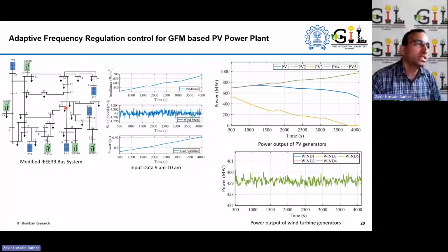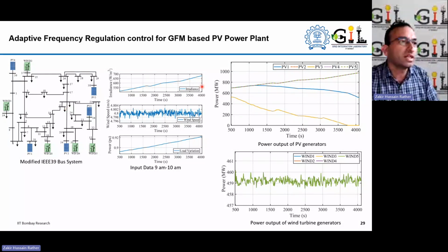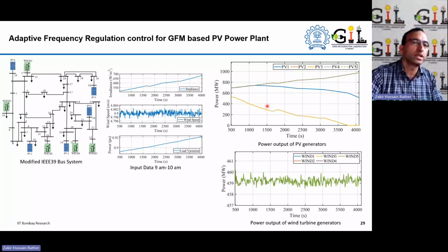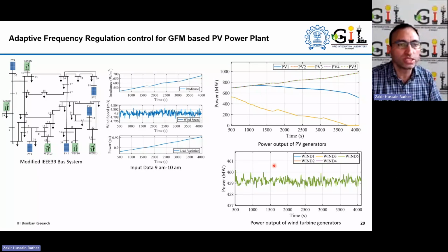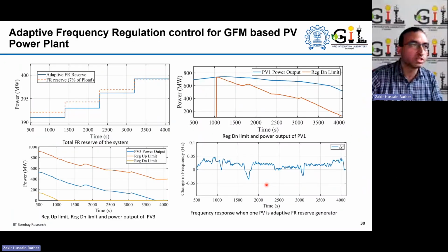So what the aim was here is the entire reserves. Of course, here there are no conventional generators, so the entire frequency reserves are provided by the solar power plants of the system, which are of the grid forming technology. So this is the irradiance variation that is considered for this window, and this is the wind speed variation, which is again considered for the wind power plants. And this is the load demand that we have in the system, which is varying. So you can see the solar power plant output is changing. I'll talk more about it in the next slide. And this is the wind power plant output in the system.